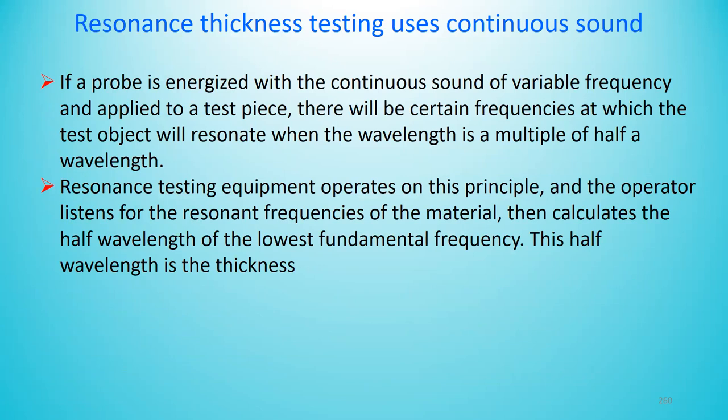The probe is energized with continuous sound of variable frequency and applied to the test piece. There will be certain frequencies at which the test object will resonate, when the wavelength is a multiple of half a wavelength.